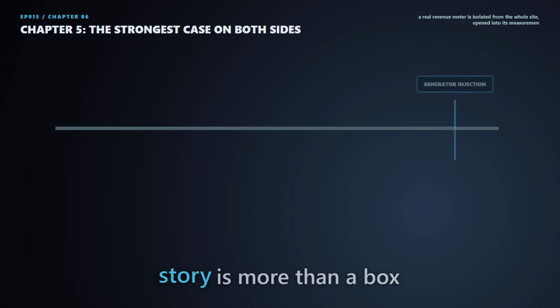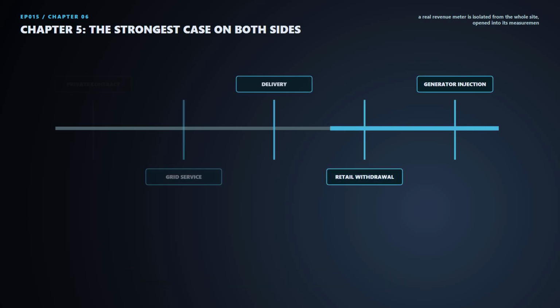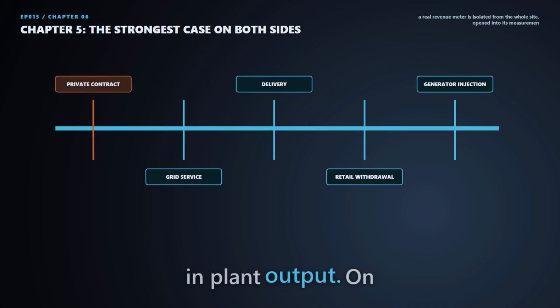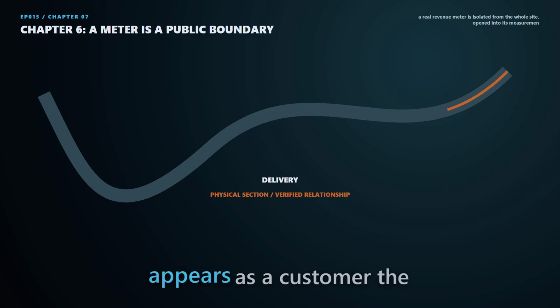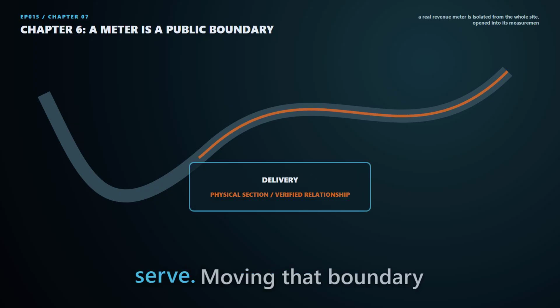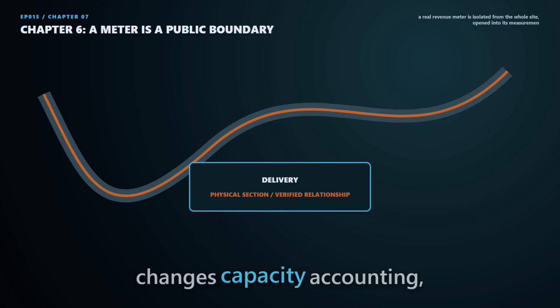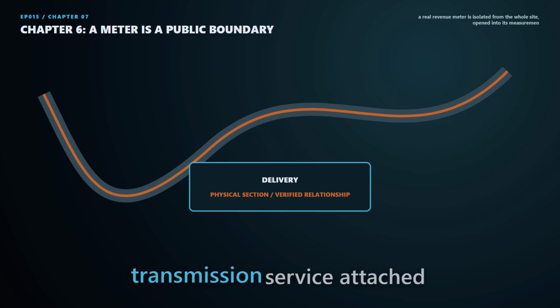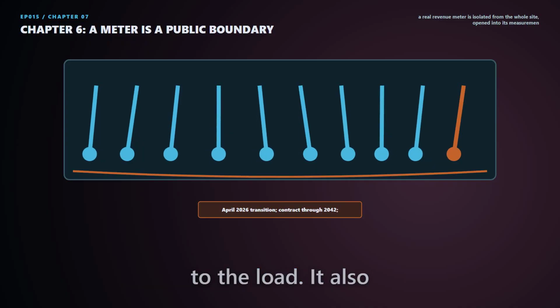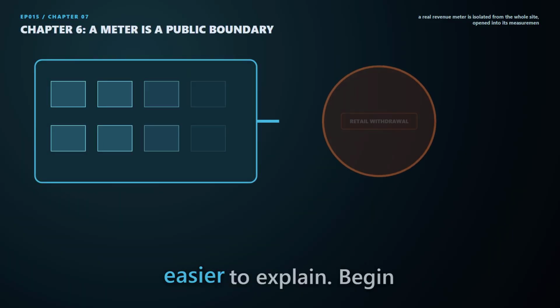The meter in this story is more than a box that records kilowatt hours. On one side, a co-located load can appear as a reduction in plant output. On the other, the same campus appears as a customer the regional grid must plan to serve. Moving that boundary changes capacity accounting, forecast treatment, and the transmission service attached to the load. It also makes the physical contingency easier to explain.